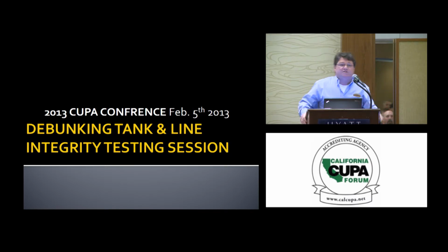See, the truth about tank testing is that one of the things I want to debunk, as the name that Sean gave us, the debunking. I might have come up with a clever name, a little more auspicious for us, but debunking is an interesting thing. But here's the deal. If on a tank test, the ATG is giving you missed results, raise the level or lower the level. Do something different. You can change the physics of the tank. Most places, the blind spot for most tank tests is 50% full. 50% full is one of the spots that's a bit of an illusion for us. So we may have to change the level in that case.